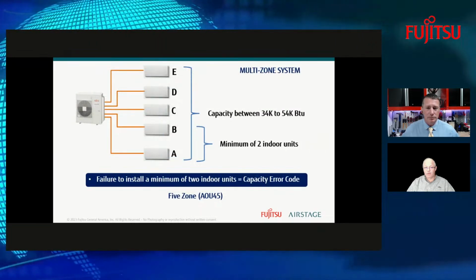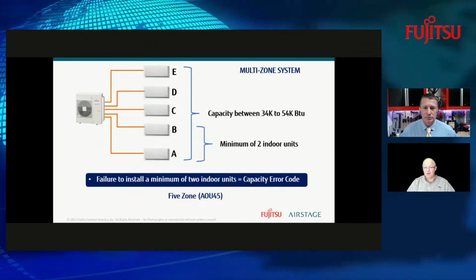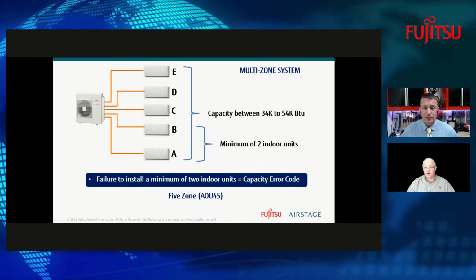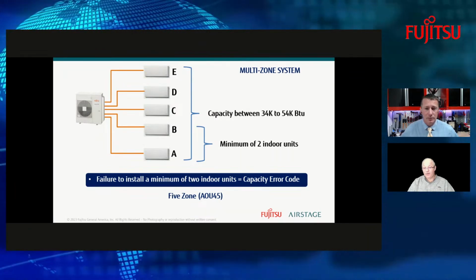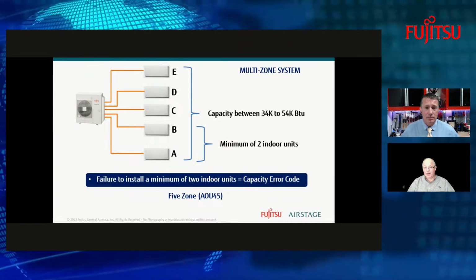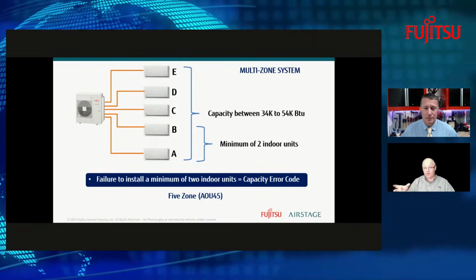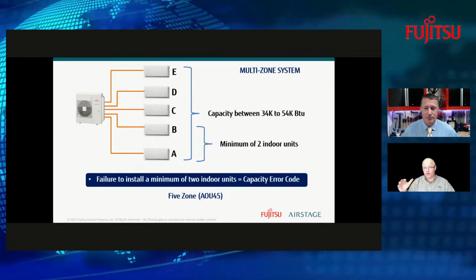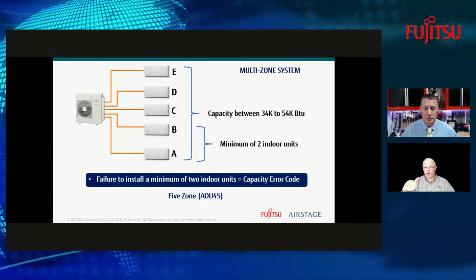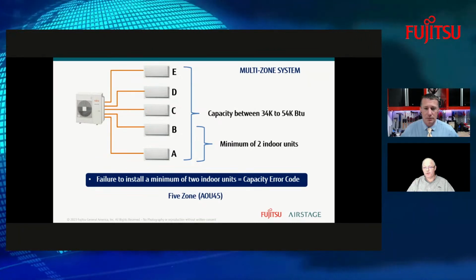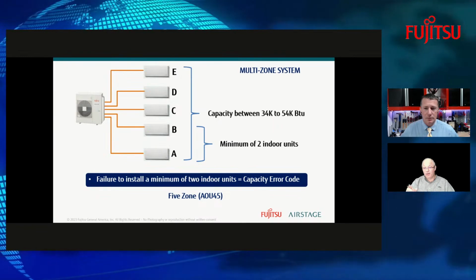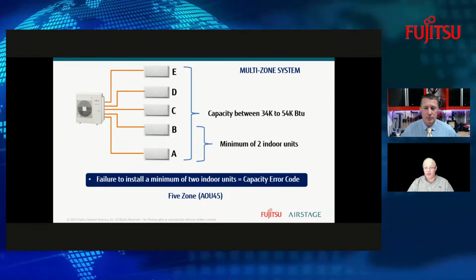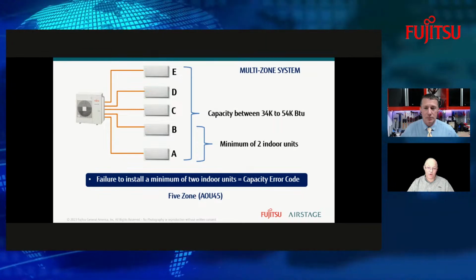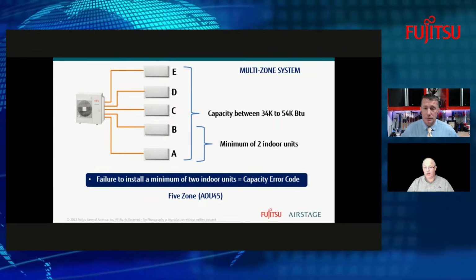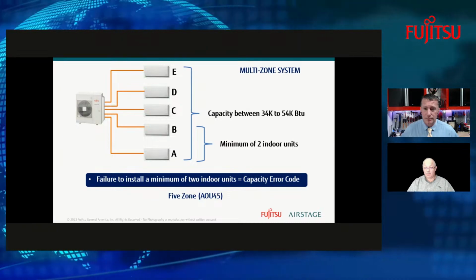All right, so on a multi-zone, just a quick note here. A lot of times when you're looking at multi-zone systems, you do have to put in a minimum amount of units on our capacity. On our AOU 45, you have to have at least 2 indoor units. You're always going to connect from the A circuit up, because the A is the bigger set of lines. The A is always for the largest indoor head that you've got, and then you work your way up this ladder with the smaller units as you move up. And you can also put in a capacity range on this particular model, between as low as 34K or as much as 54K of indoor head connectability.